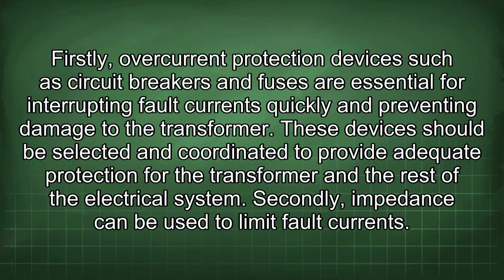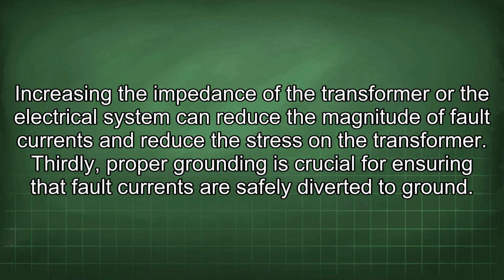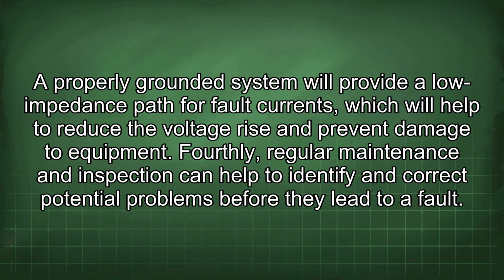Firstly, overcurrent protection devices such as circuit breakers and fuses are essential for interrupting fault currents quickly and preventing damage to the transformer. These devices should be selected and coordinated to provide adequate protection for the transformer and the rest of the electrical system. Secondly, impedance can be used to limit fault currents. Increasing the impedance of the transformer or the electrical system can reduce the magnitude of fault currents and reduce the stress on the transformer. Thirdly, proper grounding is crucial for ensuring that fault currents are safely diverted to ground. A properly grounded system will provide a low impedance path for fault currents, which will help to reduce the voltage rise and prevent damage to equipment.